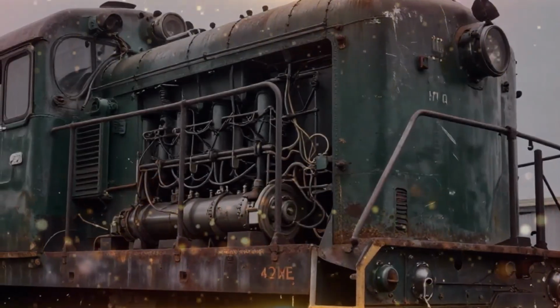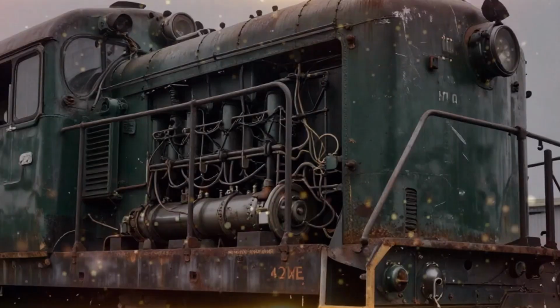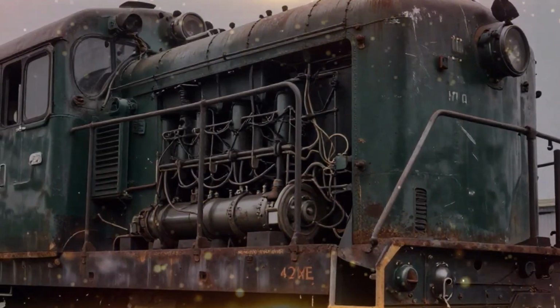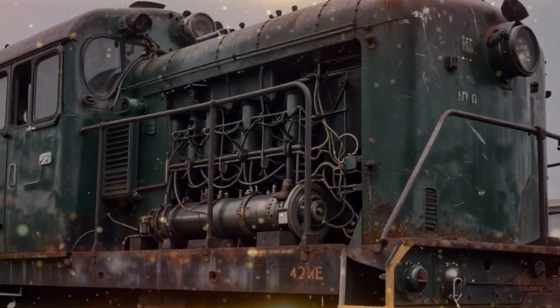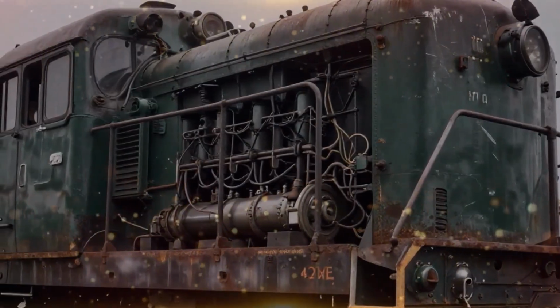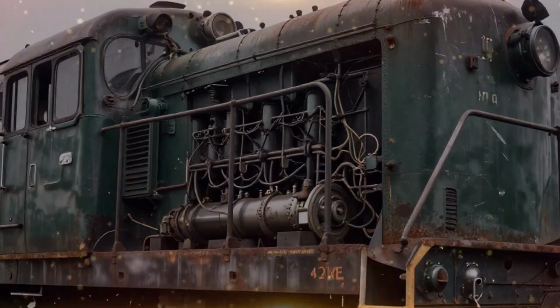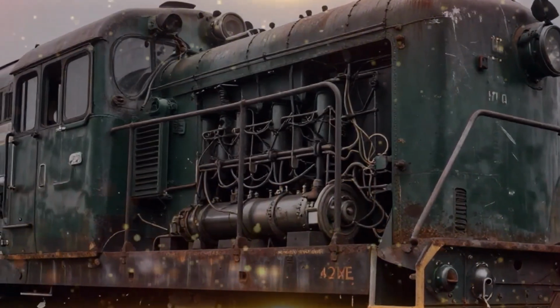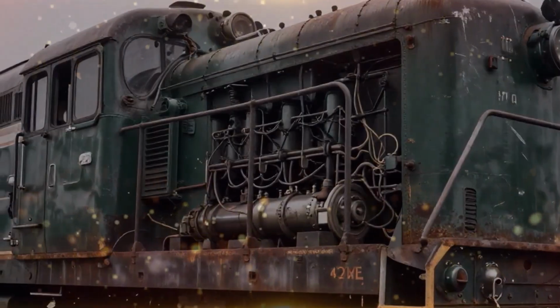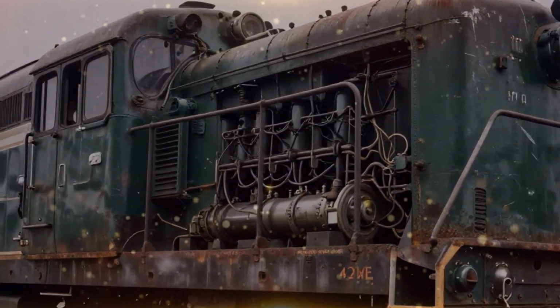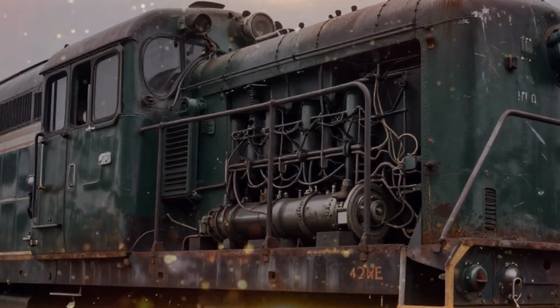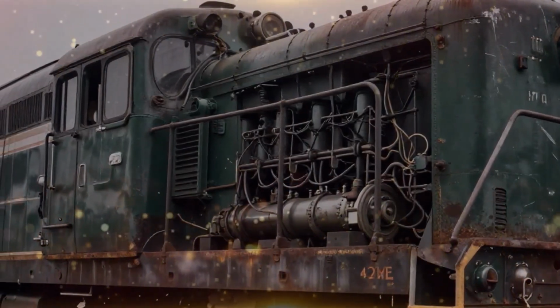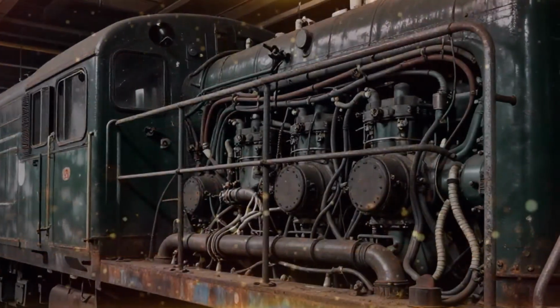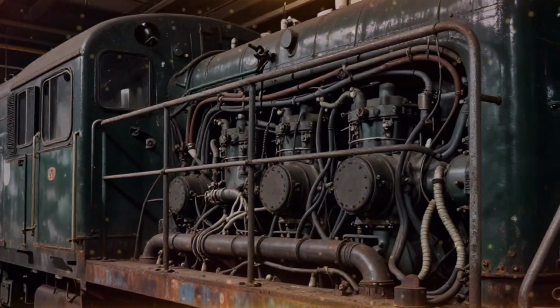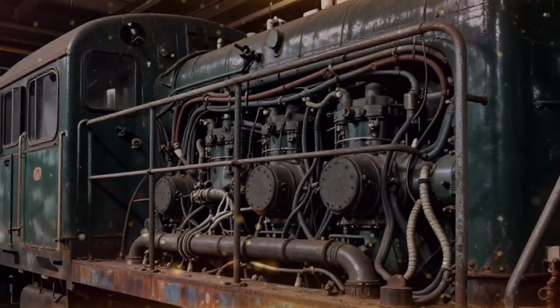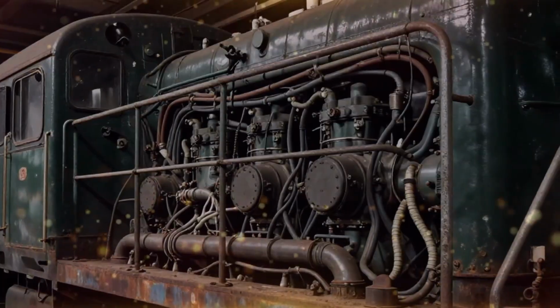But this machine operates on relay logic and pneumatics. There is no computer to tell you which sensor failed, because there are no sensors. There is only a complex network of copper contacts, air valves, and mechanical linkages. The brain of the locomotive isn't a silicon chip. It is a complex electro-pneumatic system anchored by a 162-point faceplate resistor ladder. This isn't software. It is a cabinet full of heavy-duty relays that physically snap open and shut, controlling the flow of high-amperage electricity to the traction motors.